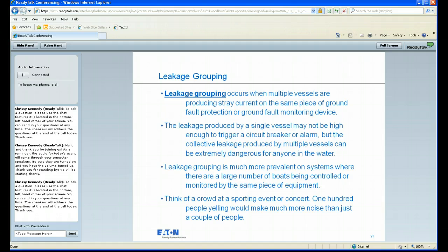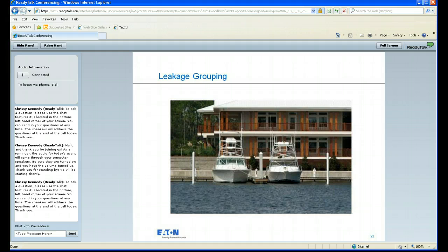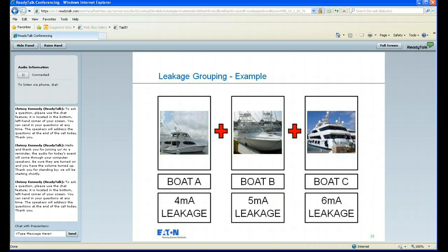Again, it's much more prevalent on systems where there are a large number of boats. If you think about it as a crowd at a sporting event, if you have a large crowd, say 200, 300 people yelling, they're obviously going to make much more noise than only a couple of spectators. So it's an example that we like to use, where 100 boats are going to produce a lot more leakage than a couple in most cases. As an example of leakage grouping, the boat on the right may be producing a few milliamps of leakage, and the boat on the left may be producing a few. So collectively, you add those together, coming off of that same protective device, and they may be enough to trip a circuit breaker.